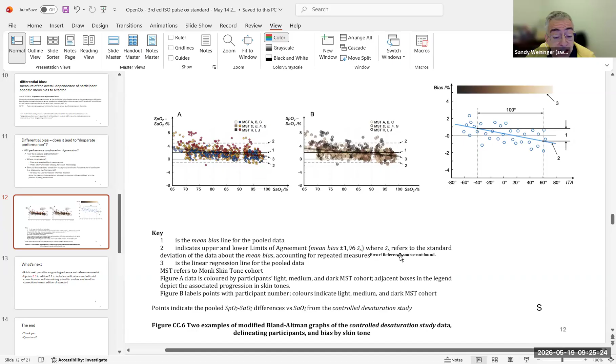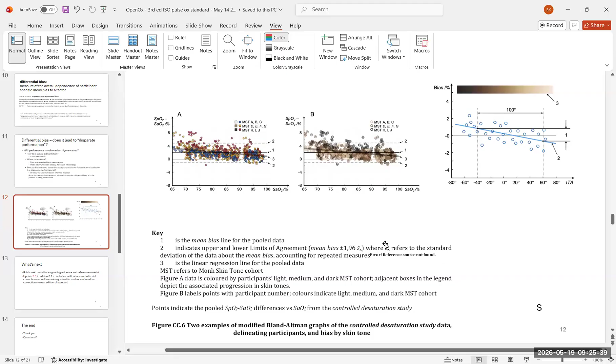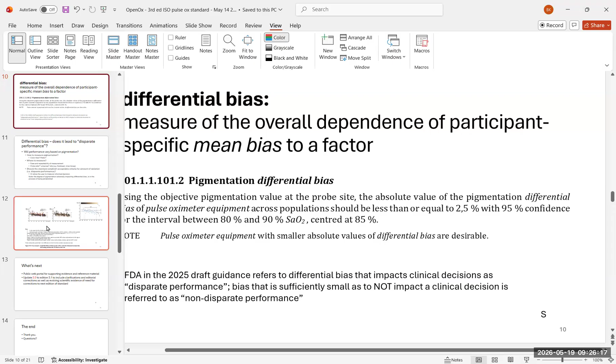Over. Next, Bob. You bet. So this is, as Sandy has pointed out, currently a should condition. So if you go back to the prior slide, recognize when it comes to the differential bias that we at the IEC ISO level are saying that it should be less than 2.5% with a 95% CI centered between 80 and 90%, at 85%. And why was all that selected? We were most aware of where the pulse oximeter might lead to an actionable clinician change. And so that's why it was selected at 85%.